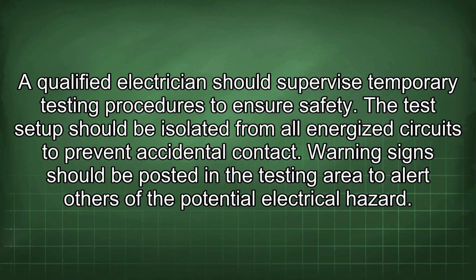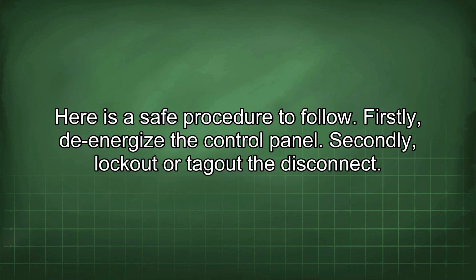The test setup should be isolated from all energized circuits to prevent accidental contact. Warning signs should be posted in the testing area to alert others of the potential electrical hazard. Here is a safe procedure to follow. Firstly, de-energize the control panel. Secondly, lock out or tag out the disconnect.